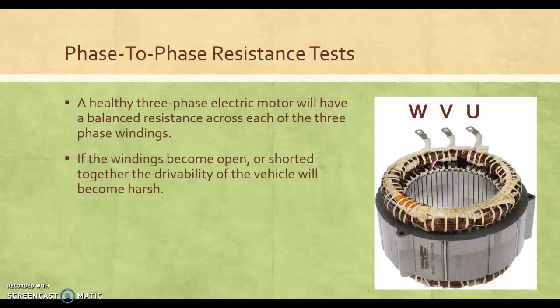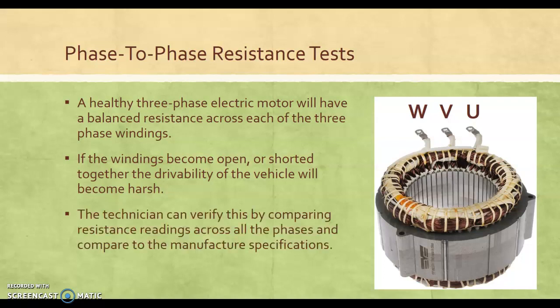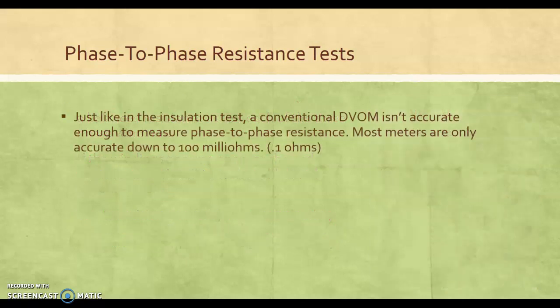A test we use is this phase-to-phase resistance test. So you compare each of the readings across all phases. Compare that to manufacturer specs, which I'll be honest are elusive. You're looking for basically within 5% is my rule of thumb. Again, if you're at 5.5%, it's not definitive that it's bad. It just gives you an idea of the health of the stator.